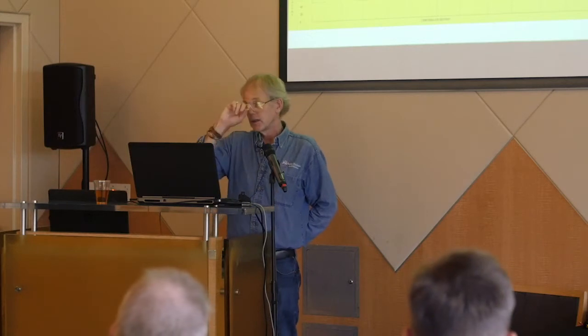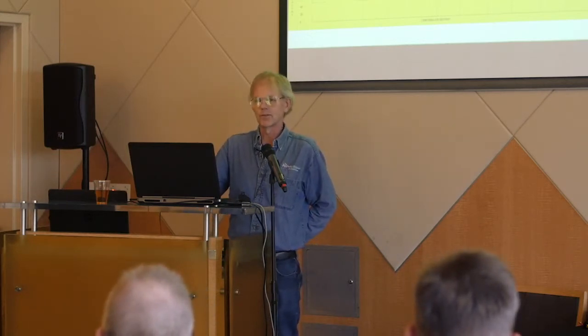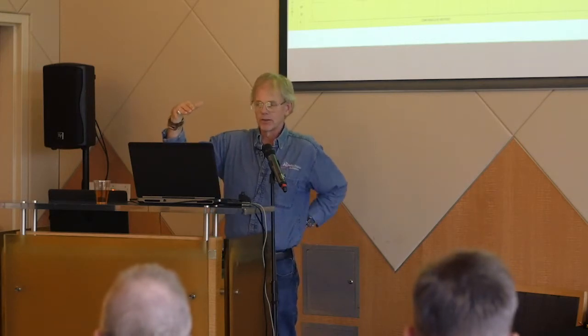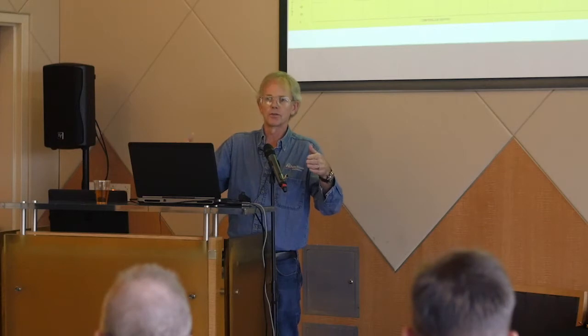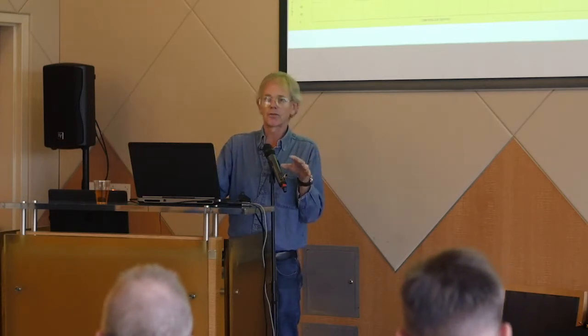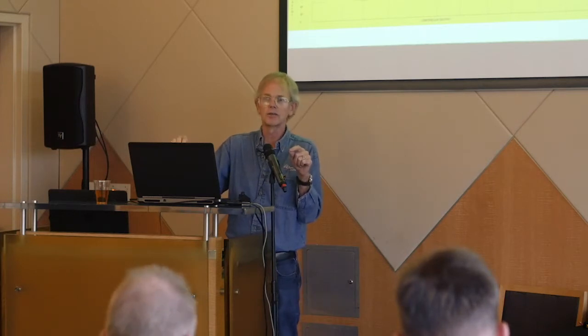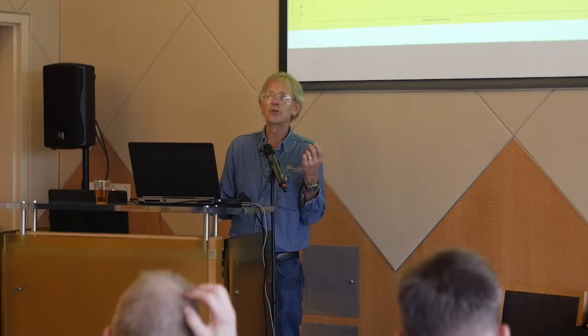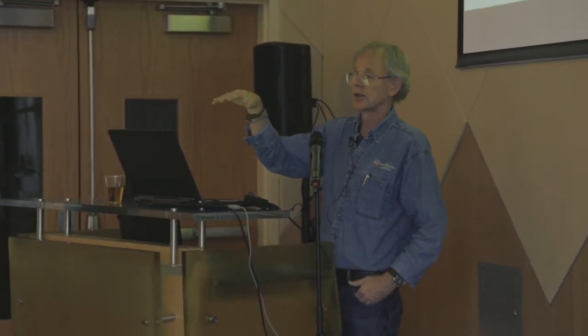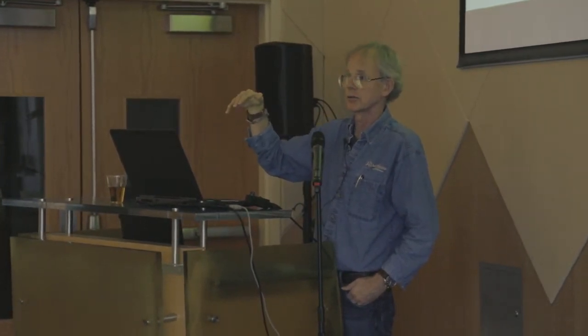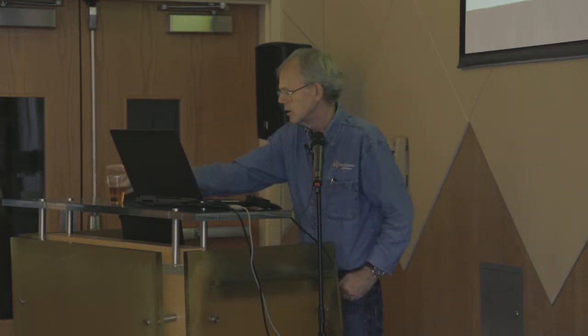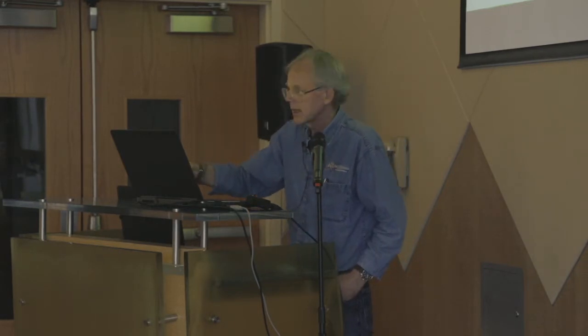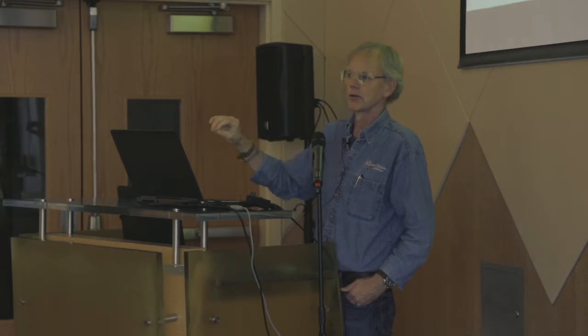Yeah, there's different. The tuning theory is a mathematical relationship that is basically about the lags, the thermal behavior, the responses and the frequencies of the system. What varies from manufacturer to manufacturer is the algorithm they use to calculate the output of the PID loop. There's at least 2 common algorithms, and if you download that PID paper from Control Engineering, I think they have an article that talks about 4 different PID algorithms. Since different vendors use different algorithms, the proportional band you'd use on one vendor's system is not going to be the right number on another vendor's system.